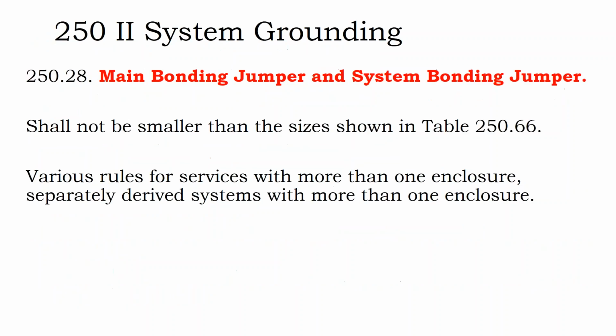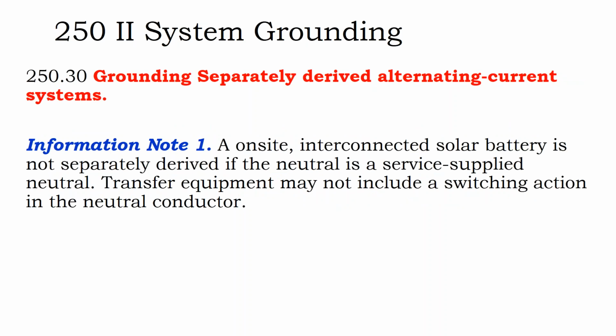But that doesn't mean that your grounded conductor is connected at multiple points to ground. It's connected at one point to ground. There are some minimum size requirements for your neutral. It says an on-site interconnected solar battery is not separately derived if the neutral is a service neutral. Transfer equipment might not include a switching action in the neutral conductor. So we talk about separately derived systems.